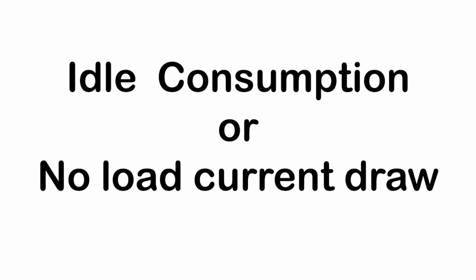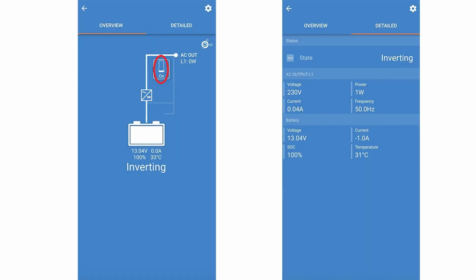However, the inverter is still powered on, so it still sucks some electricity out of your DC battery. Sometimes not much, but still something that might add up if left on for an extended period. Something to look for on an inverter is an easy way to turn it off when it's not in use. Some inverters allow a Bluetooth phone app to remotely control them, turning them on or off if and when needed. Some inverters have a power saving feature, that is, when there is no AC demand being made on the inverter, they go on a sort of low idle power saving mode. But again, it's still power you'd rather not lose if possible.